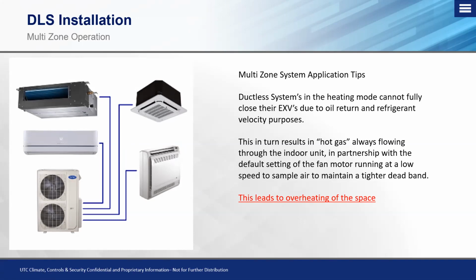And this is also something that we need to take into consideration when we are applying these systems, especially in areas with different thermal loads, such as different temperature requirements, or areas that have greater heating loads than others that are on the same system. Okay, but a good rule of thumb is understanding that the EXVs do not shut 100% in heating mode. Paired with the indoor fans running at a low speed, this leads to overheating of the space. It's a misapplication issue.